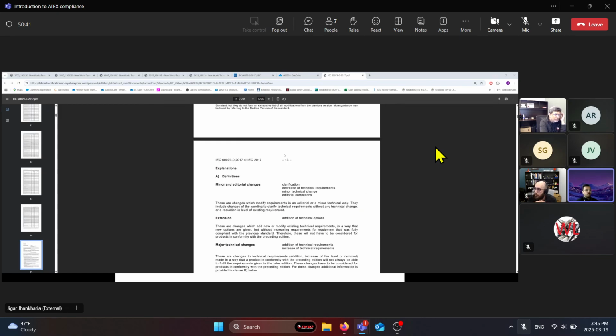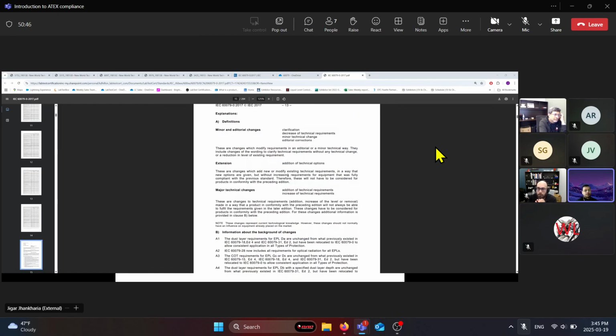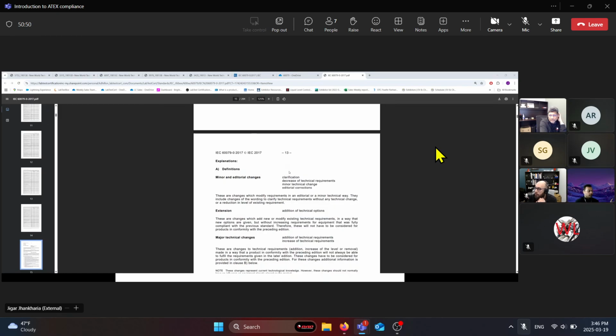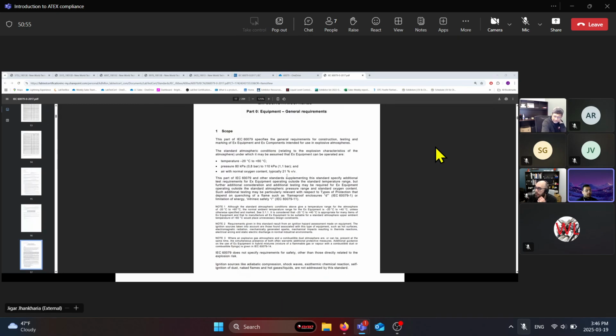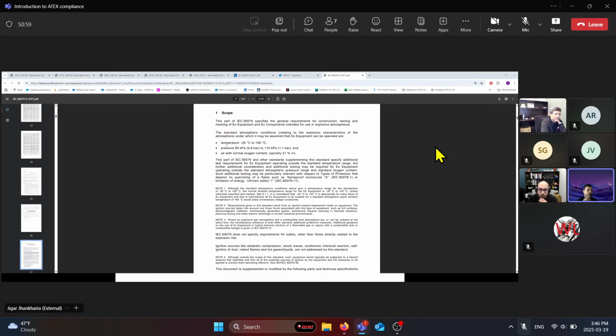So usually we opt to use the checklist for the newest IEC standards because it covers the old versions of the standards as well. Let me go to the scope. You can see it talks about the general requirements of construction, testing, and how you would mark your equipment. When we talk about general construction, it references the different methods of protection, for example increased safety. There is a section in here for IP rating as well, which calls out the other standard. When you look at 60079-7, you'll see certain sections call out -0, for example thermal endurance of the product. Does it meet the requirements of the tables provided in -0? So basically all the different methods of protection in IECEx and ATEX reference back to -0.